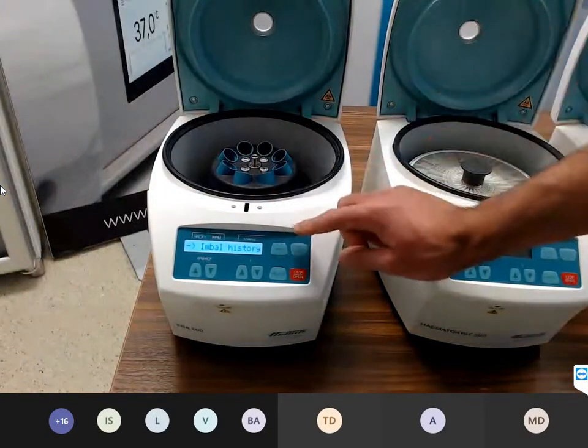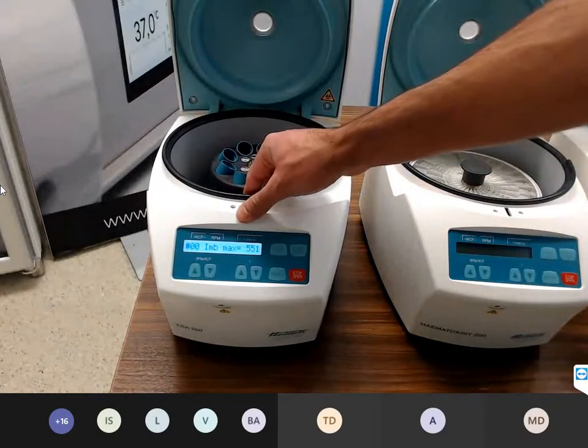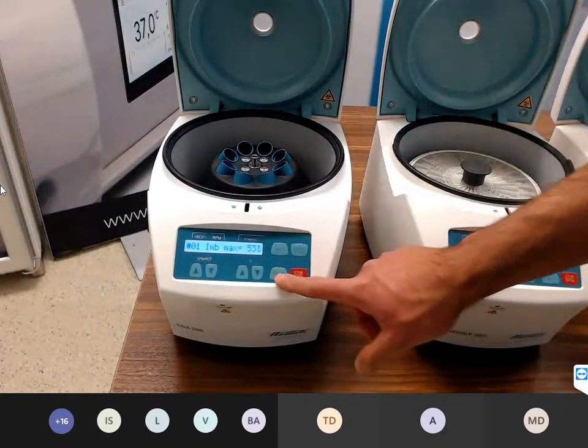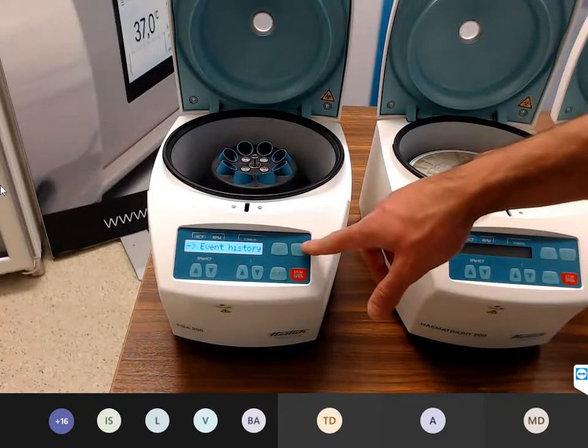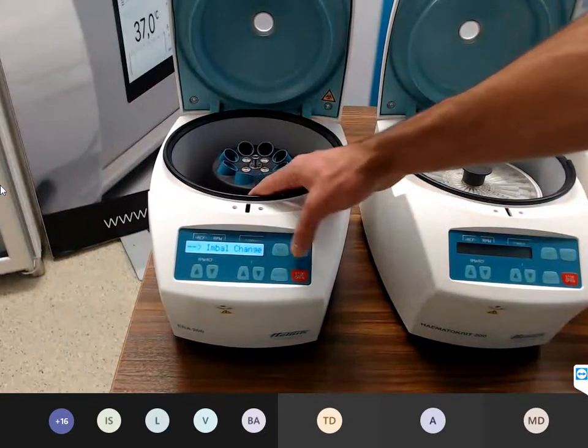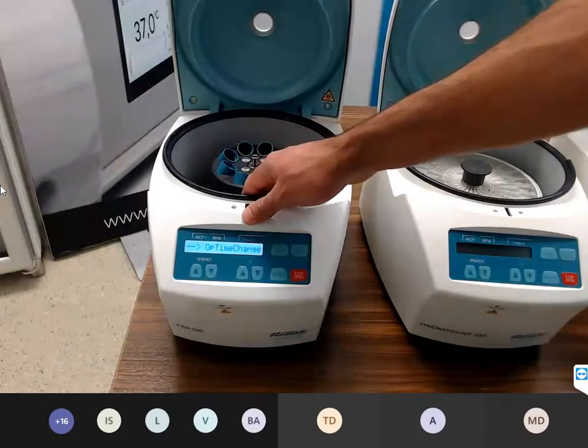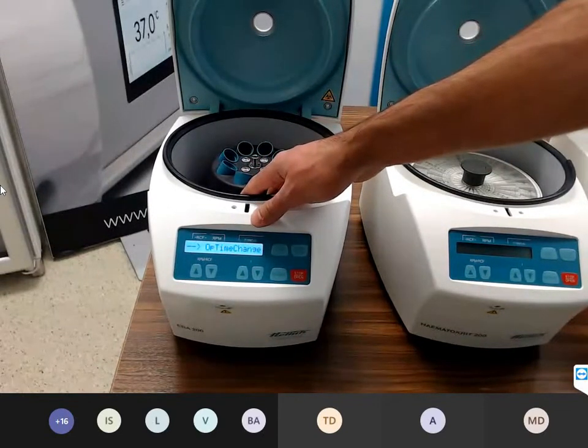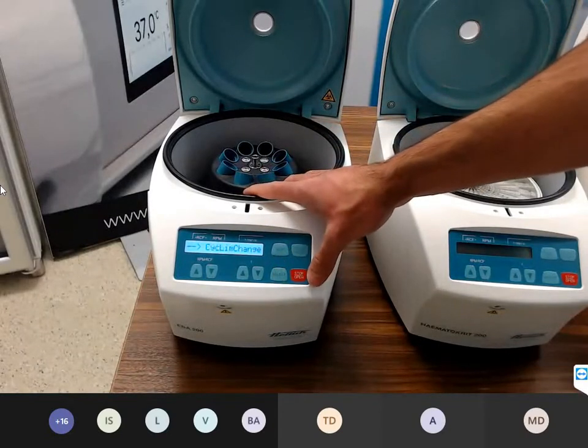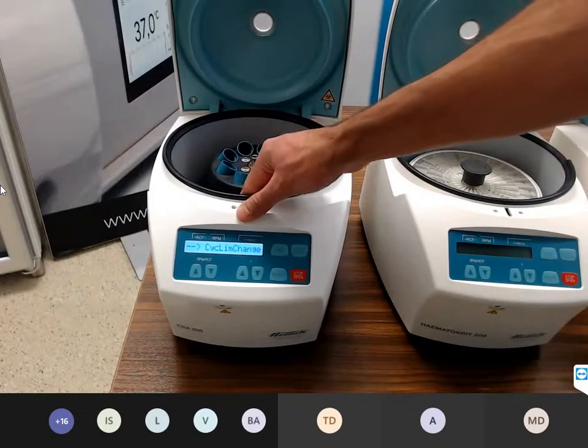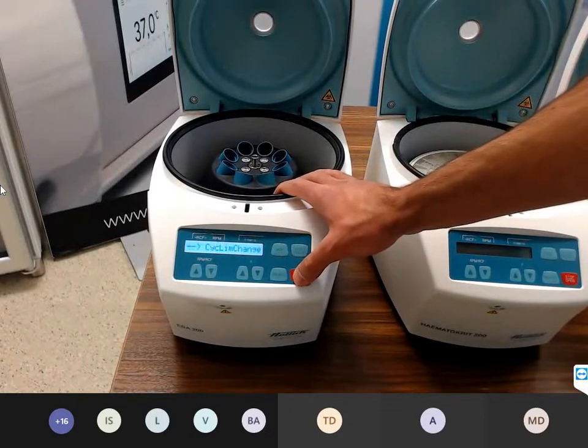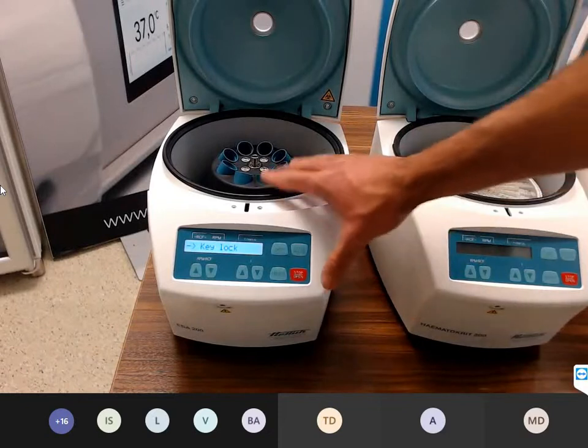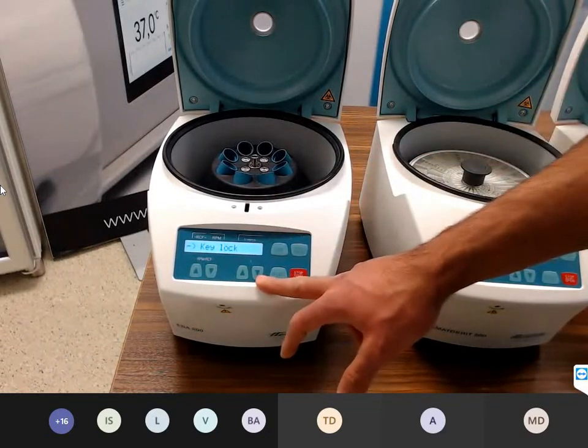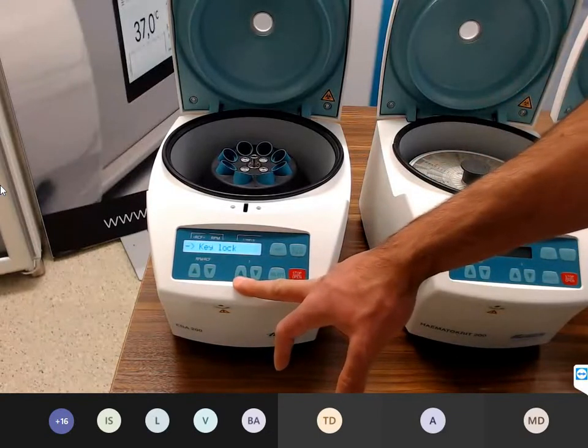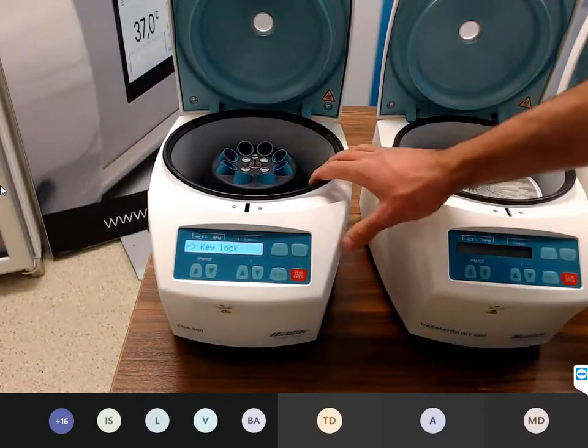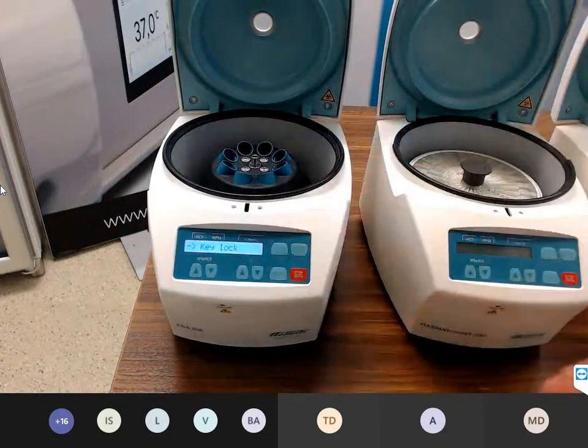We can read the imbalance history also. What was the last imbalance value here? And the event history means when was the last imbalance setting, when was the last time setting changing, and when was the last setting of the cycle counter. And here, the last one, we can lock the keys for the customer or for the employees of the customer. The customer can only start and stop the device. All these keys are locked if you set the lock.